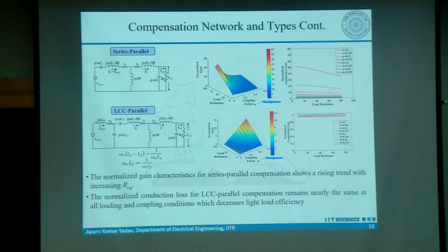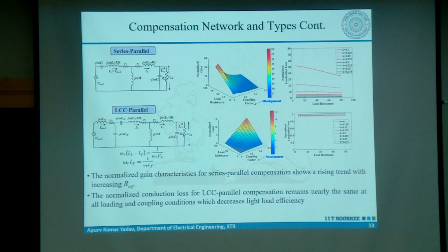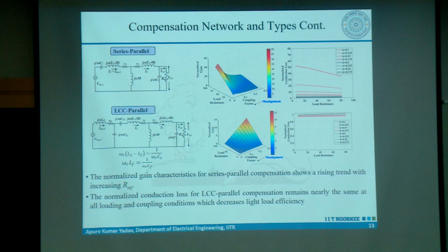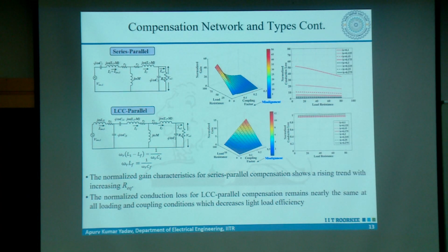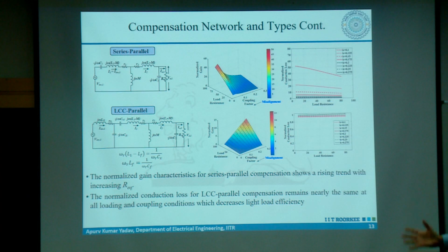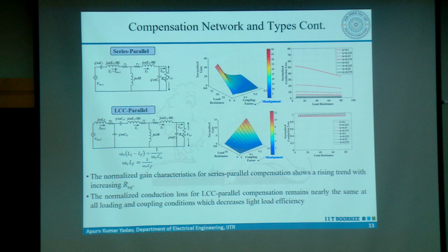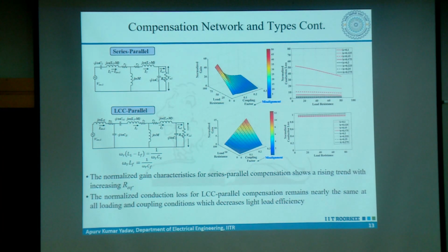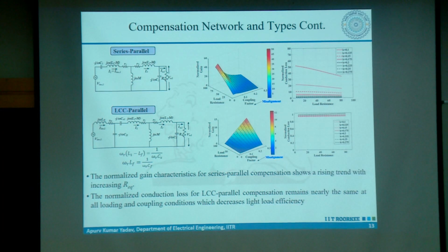With a foreign object body present, the coupling varies, and there's literature on FOD—foreign object detection—using the change in impedance when a foreign object comes into the picture. So the field distribution definitely changes with a different medium, and all parameters won't hold true. You have to design your system so that if a foreign body appears, you either switch off the system, or if you can still operate it, you need to study that case.